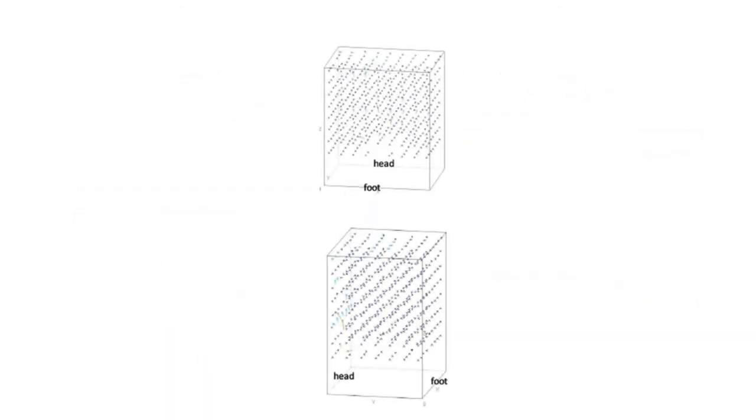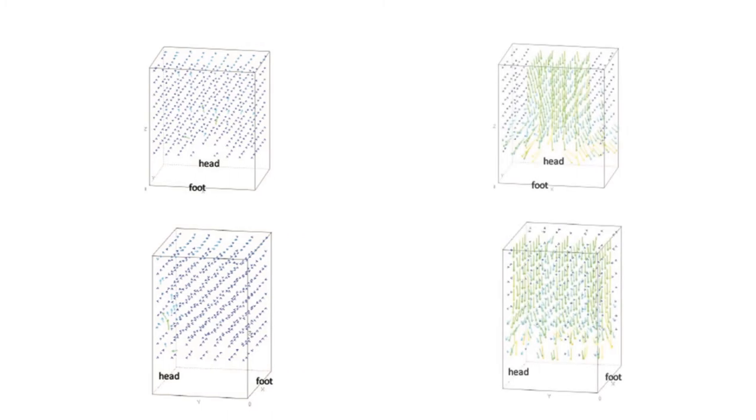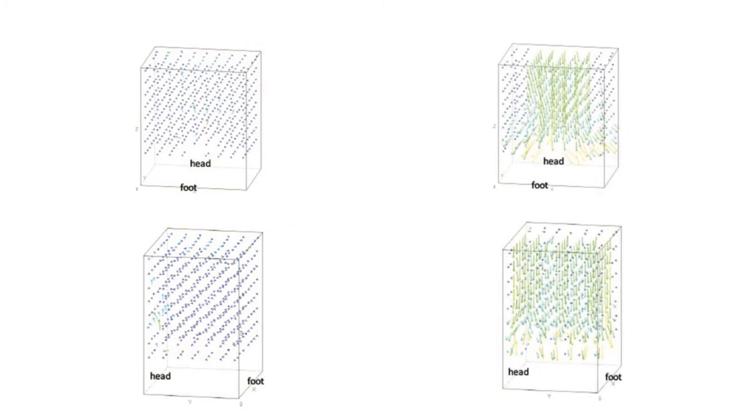The results showed that the forced air warming system created convective airflow, causing air to recirculate around the mannequin instead of simply passing over it. But restoring laminar flow counteracted this effect.